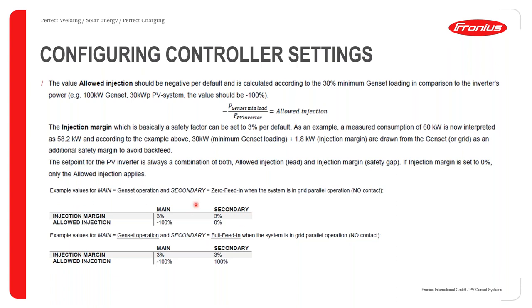There are two input case scenarios. In the first, the genset is the main operation and the grid is secondary — achieved using a normally open (NO) contact. With genset running, injection margin is 3% and allowed injection is minus 100%. When the grid returns, the genset switches off via the ATS, and the allowed injection changes — either to 0% for municipalities that don't allow feed-in, or up to 100% for those that do permit grid feed-in.